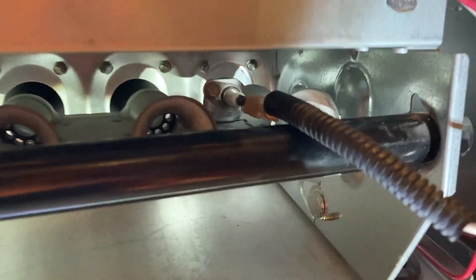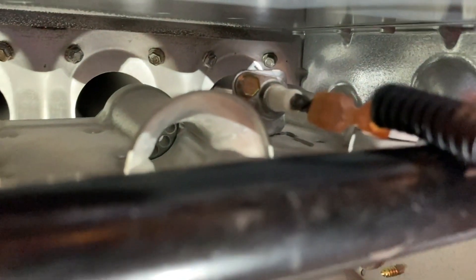This is a very important safety feature of the system, part of your ignition system. What happens over time: you have a porcelain part of the sensor that can crack. You also have the electrical lead that provides the electrical current, and that can become very oxidized, corroded, or develop a layer of soot — very similar to ash buildup in your fireplace or chimney.